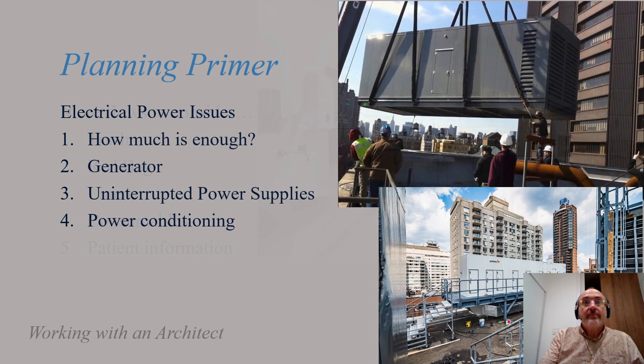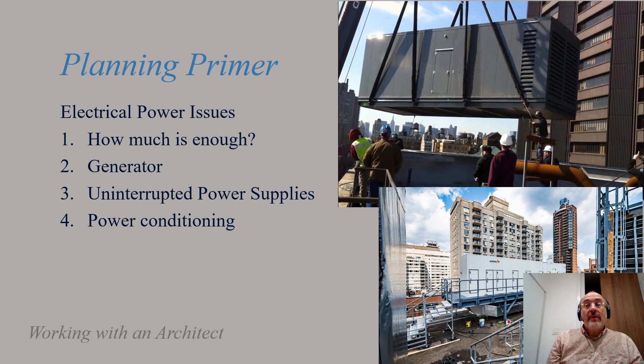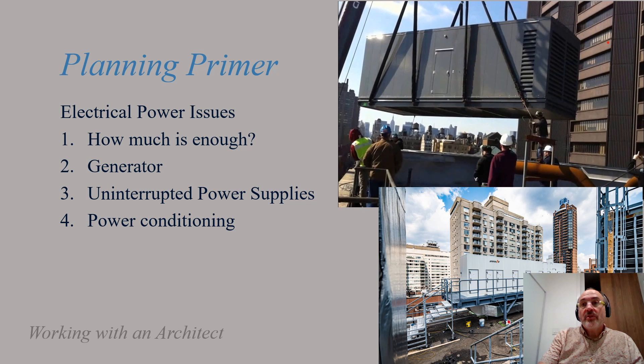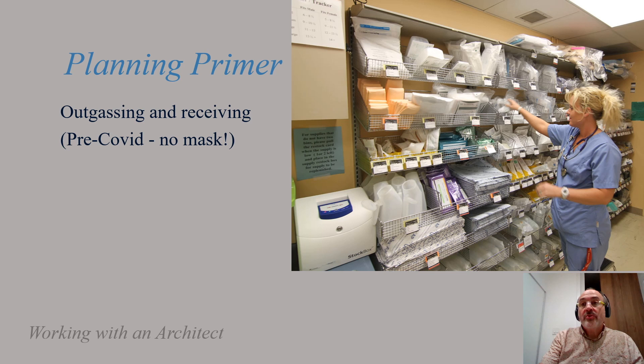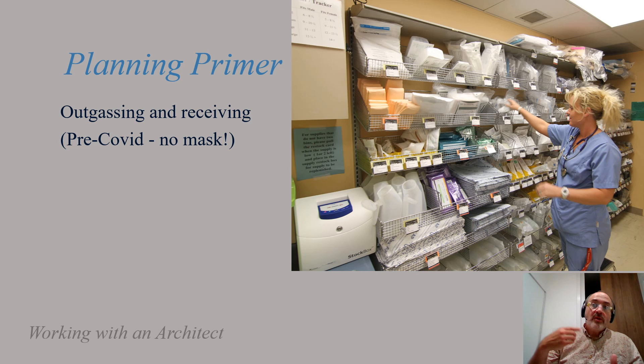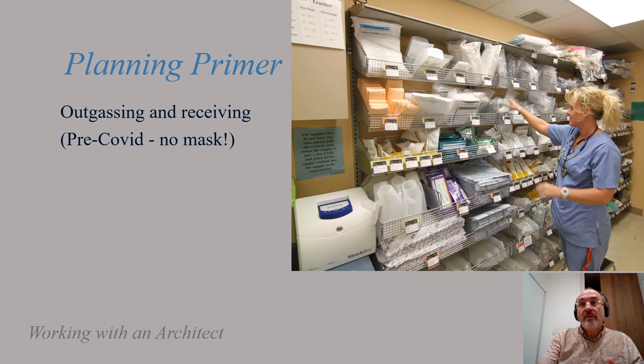Electrical power issues and uninterrupted power supplies must be part of your early survey to keep automated equipment running at the right power all the time. On placement: make sure the generator and air handler on the roof are as far apart as possible so you aren't polluting your own air stream. Put negative pressure in your storage area and rotate materials so older items move forward and newer materials go to the back, allowing materials to out-gas for a week to two weeks before entering the lab.